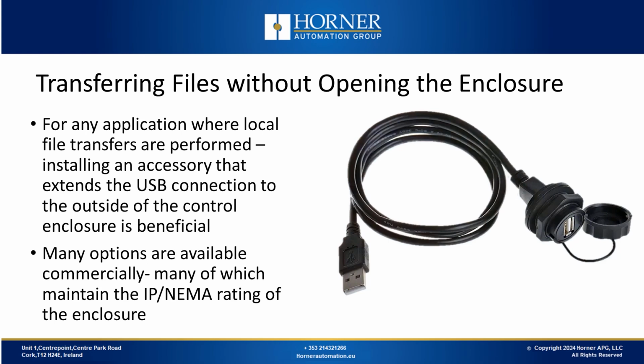If you want to transfer files between microSD and USB, then a USB extension cable like the one shown, that can extend access to the USB port to outside the control enclosure, can be very useful. Many of these cables also maintain the IP or the NEMA rating of the enclosure. With these cables, you don't need to open up the control enclosure. Instead, you unscrew the cap over the USB port, plug in the drive, and then from the touchscreen, you can perform the functions that we will show in today's demonstrations.